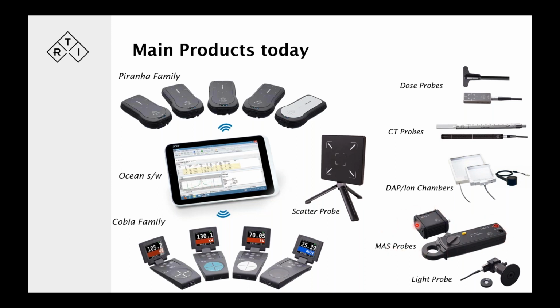We've got mA probes as well, apart from the MAS-1, which is an invasive one. We have a non-invasive MAS-2 probe that clamps on to the high tension cable. We'll look a little bit closer at that later on. And one that isn't shown here is the mA test point cable. We'll look at that as well in a while. And finally, there's a light probe that doubles as measuring the luminance from a screen to see that the output from the screen is as it should be, that it conforms to the values in the test patterns that are determined for that. And using a small diffuser, fitting that onto the light probe gives us the possibility to measure the ambient light and the collimator light to verify the collimator light intensity.